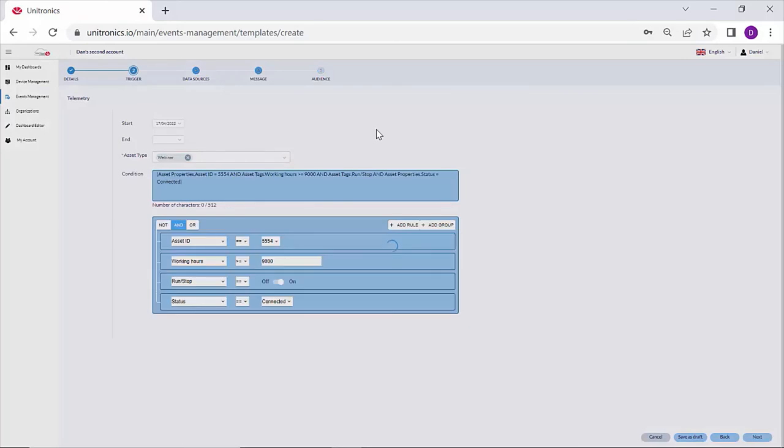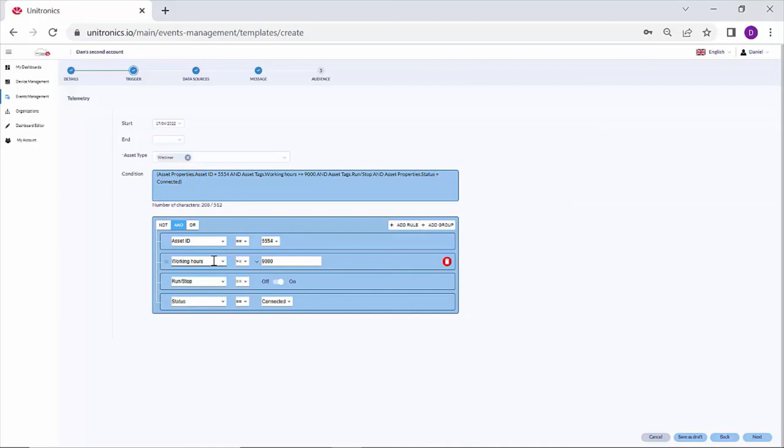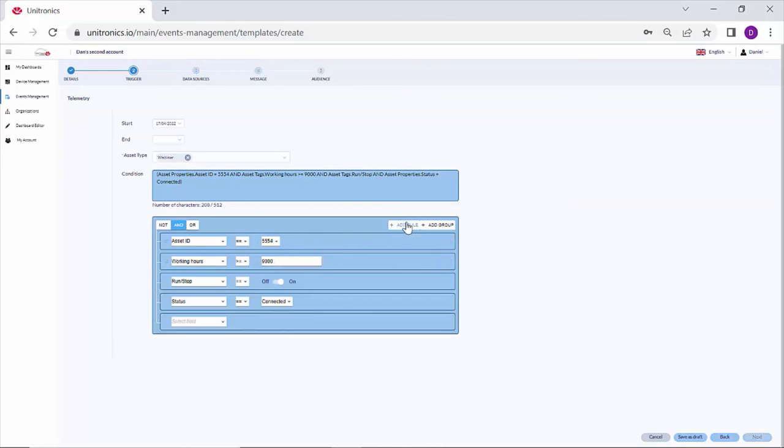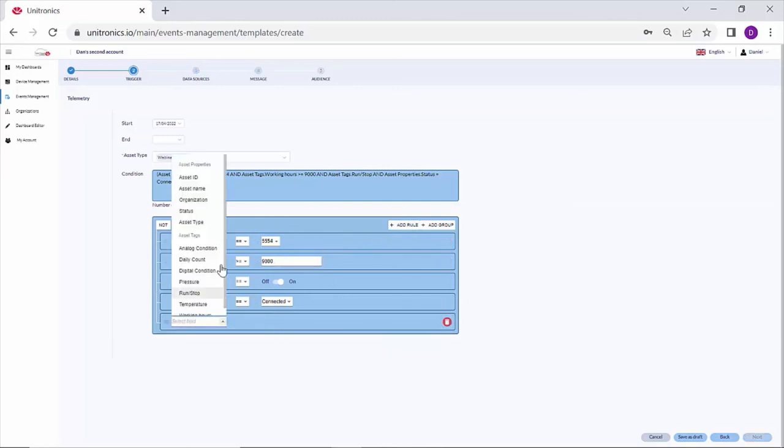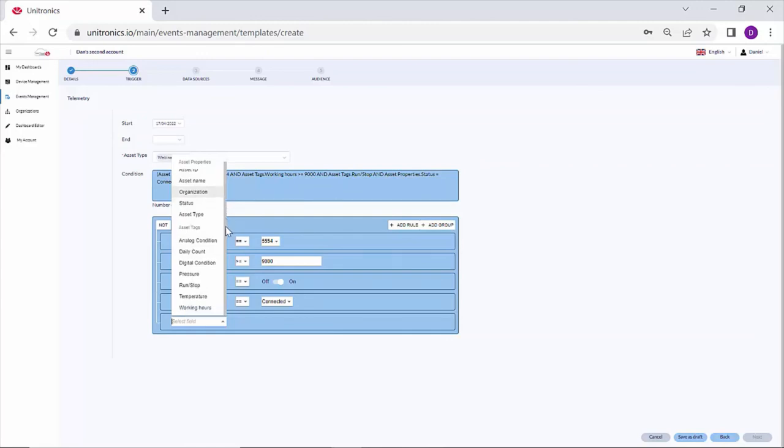Navigate to triggers. And in the rules section, you can see I'm referencing some tag data from this device, specifically the working hours being greater than nine thousand. I can add another rule and take a look at the fields available. We have the asset properties that we previously had, but we also have the tags from the PLC. And again, we can reference these here.